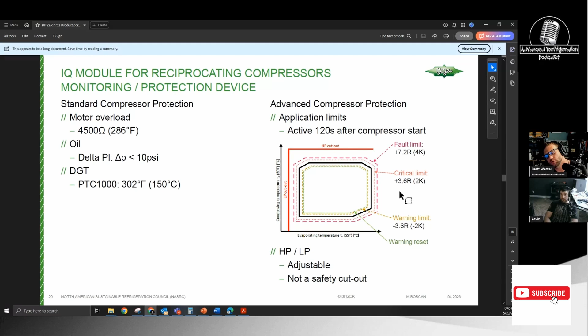I don't think I understand, are you talking about the suction return temperature coming back from it? When you're unloading all three heads you have very little flow going through the compressor, so it heats up real quick. Oh shit, yeah, because it's still suction blocking, right? Correct, it's still a suction blocking compressor.